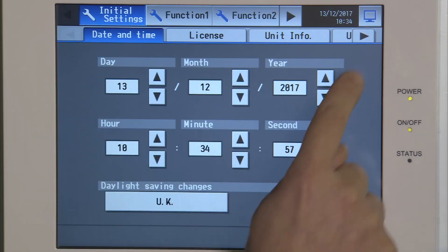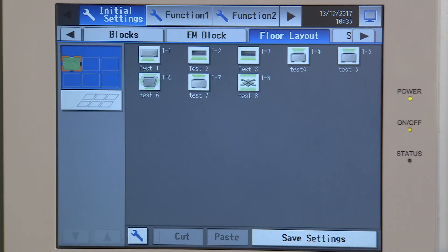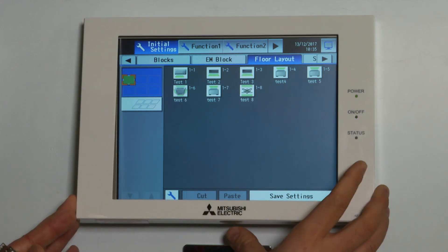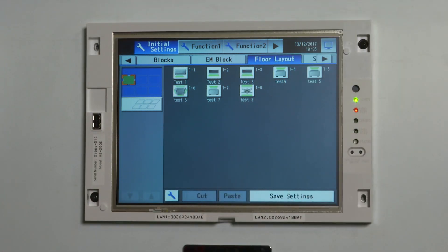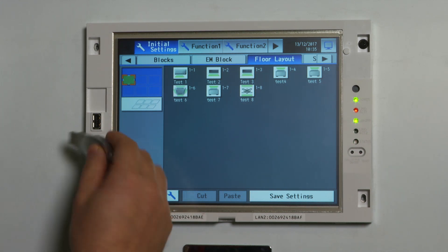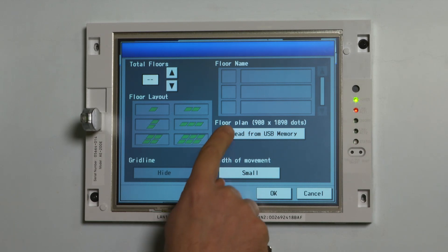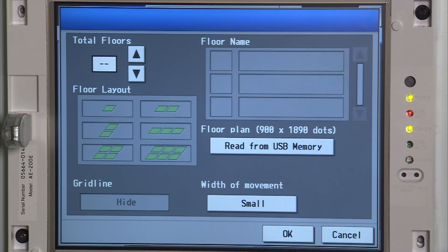On the initial settings, scroll across to floor layout. Take the front cover off — you may need to undo the screw at the bottom. Insert the USB stick with the drawing on it. Click on the little spanner key. This drawing needs to be 900 by 1890 dots and needs to be a GIF file.